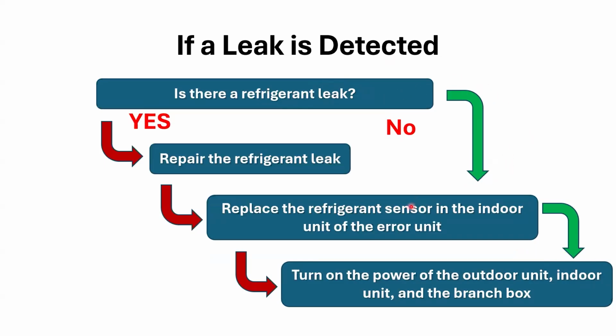Let's go down here. Replace the refrigerant sensor in the indoor unit of the error unit. Well, replace or test, right? We just went through the testing process. I would probably test it first before just jumping in and replacing it. And from there, turn on the power of the outdoor unit, indoor unit, and branch box. Power sequence matters on the branch box systems. If everything's powered from the outdoor unit, then we power on the outdoor unit. But if it's separate power, where the branch box gets separate power from the outdoor unit, we always power the outdoor unit last. Now, if there is a refrigerant leak, yes, repair the refrigerant leak, obviously, replace the sensor, test it if needed, right? We test first and then replace as needed, and then turn power on.